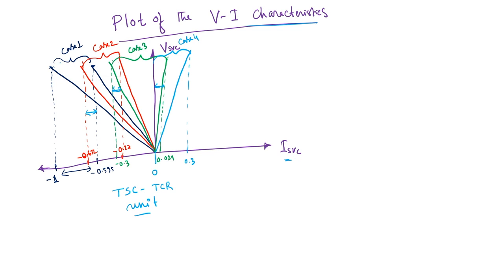So with this TCR control, we can operate it either in case 1, or in case 2, or in case 3, or in case 4, and we have a capability to provide here to here that much of this VAR. This is what is called the control range of this particular TSC-TCR unit.